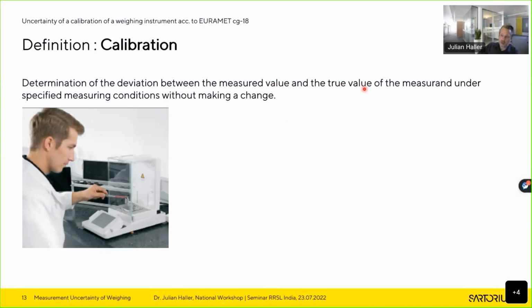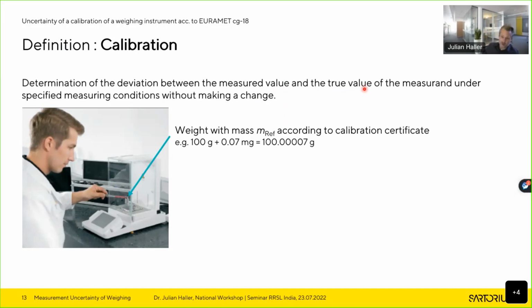So what does that mean for a weighing instrument? Well, actually, you put on a weight. And as Mr. Dixit said in the introduction, the weight is of course so important for the calibration of a weighing instrument. You do know this reference weight, because usually you have to use a calibrated weight. So you know, for example, this 100-gram weight has a conventional weighing value, or let's say true value, of 100.00007 grams, for example. And now you read the indication from the balance, in this example, 99.999 gram.